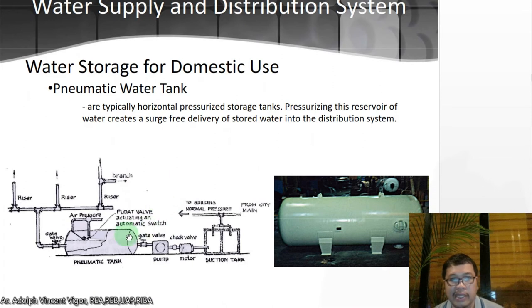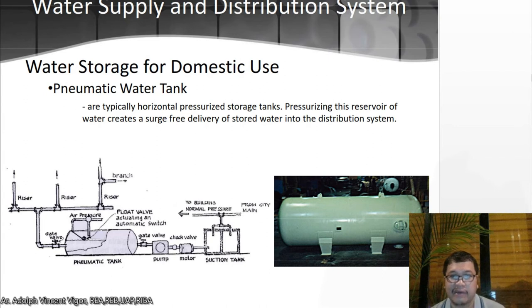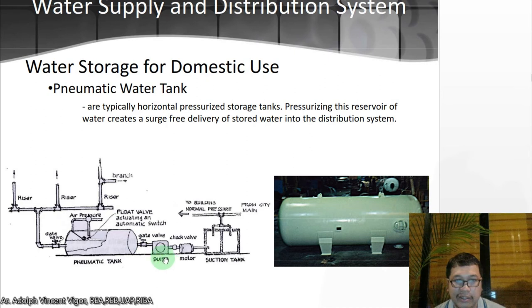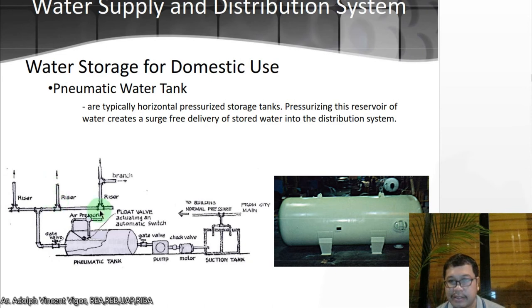Then you have the pneumatic water tank, which is typically a horizontal pressurized storage tank. Pressurizing this reservoir of water creates a surge-free delivery of stored water into the distribution system. It includes a pump, gate valve, check valve, and suction — air pressure is built up in the pneumatic tank, and when you open it, water flows to the different branches and risers.